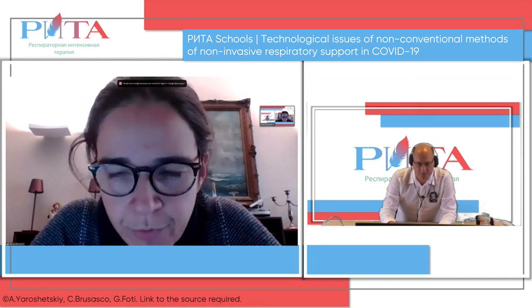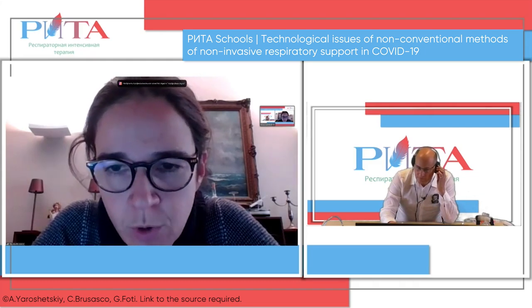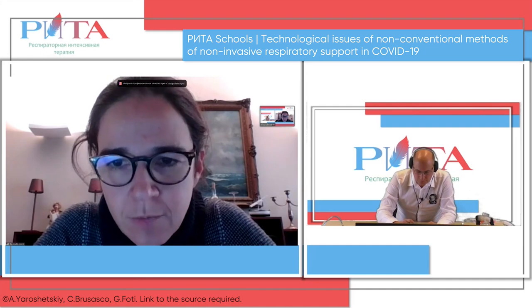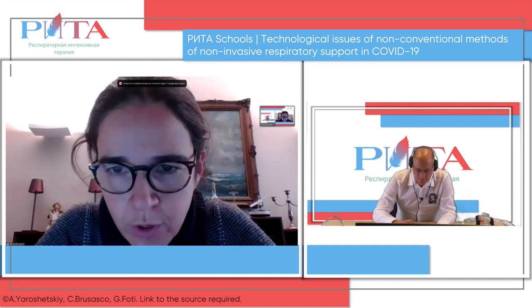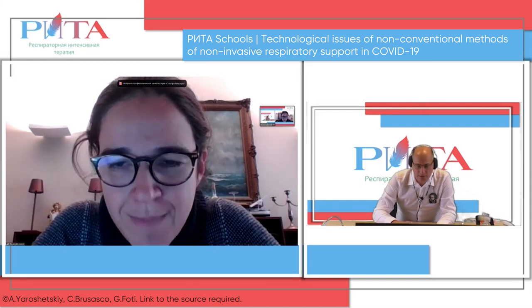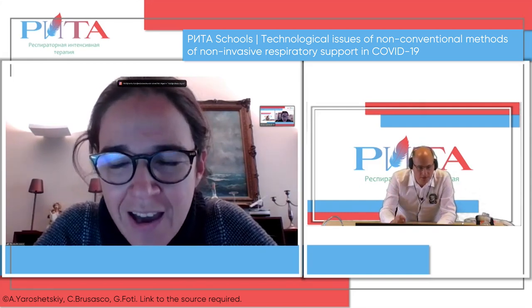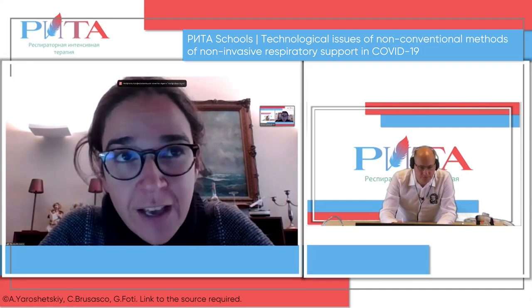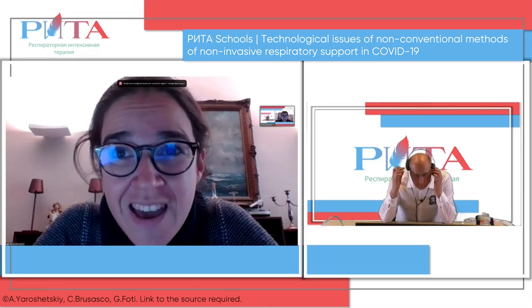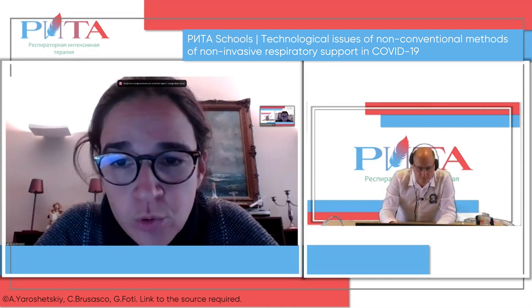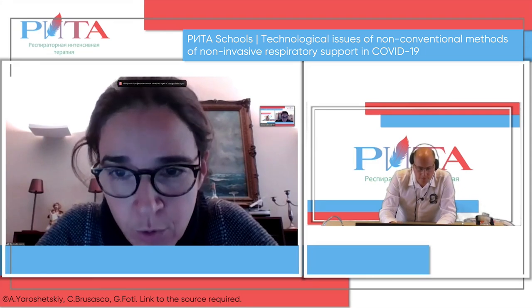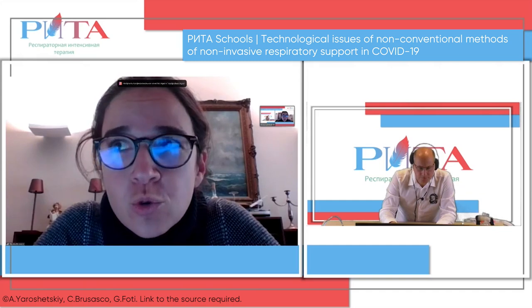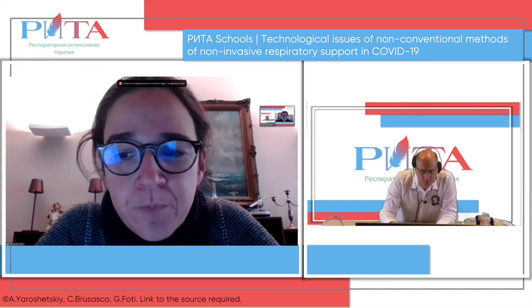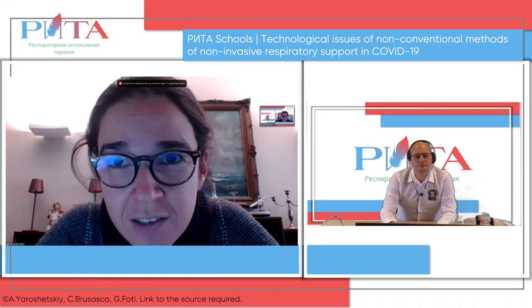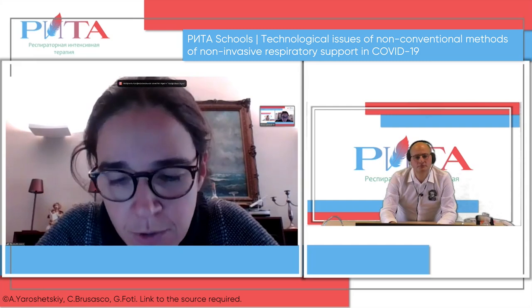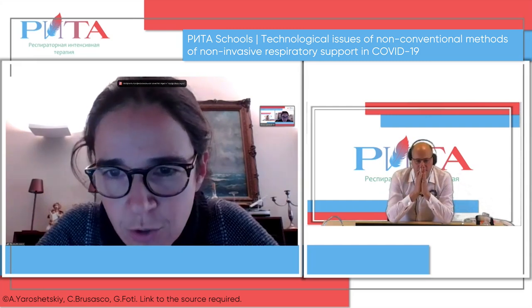I think that if we want to perform continuous positive airway pressure on a patient, the only system we should use is a Venturi system, for sure. The main point is a Venturi system with high efficiency and effectiveness - it has to be a high flow Venturi system that generates very high flow. You have to use the Venturi system that performs the highest airflow output possible. This is the key message.